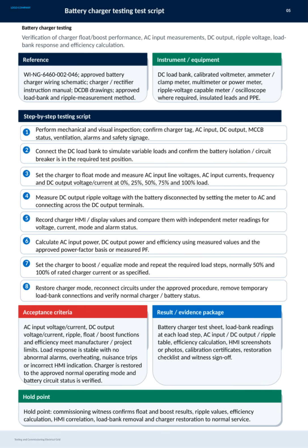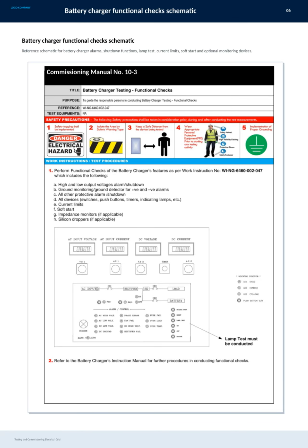Here we have the battery charger functional checks schematic, which is crucial during testing and commissioning of the electrical grid. This schematic serves as a reference for several important functions, including alarms, shutdown procedures, lamp tests, current limits, and the soft start feature. Additionally, it covers optional monitoring devices that help ensure the charger operates reliably. Understanding this schematic is key to performing thorough and effective commissioning, as outlined in Commissioning Manual number 10-3.